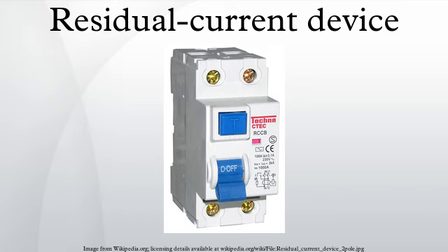Testing. RCDs can be tested with the built-in test button to confirm functionality on a regular basis. RCDs, if wired improperly, may not operate correctly and are generally tested by the installer to verify correct operation. Use of a solenoid voltmeter from live to earth provides an external path and can test the wiring to the RCD. Such a test may be performed on installation of the device and at any downstream outlet.